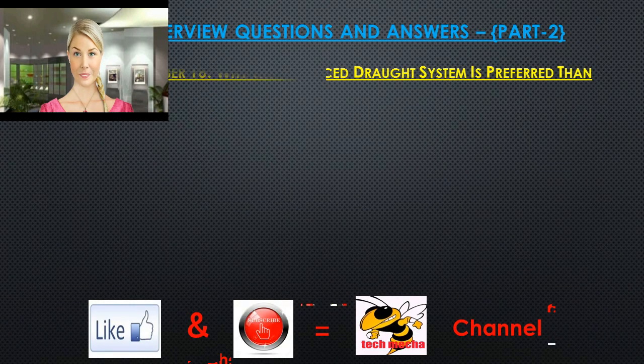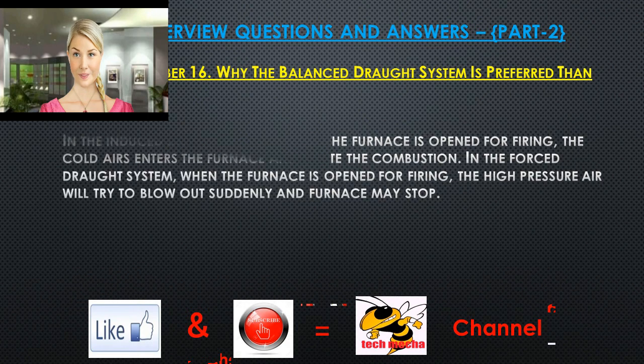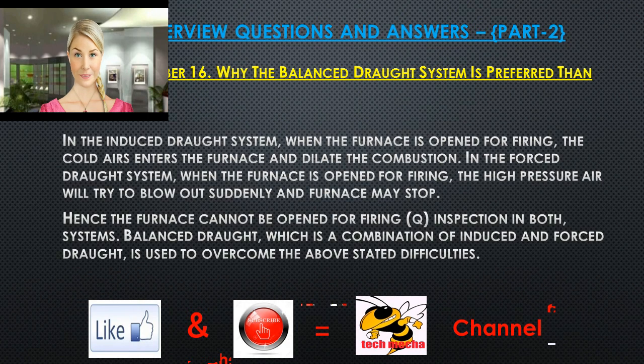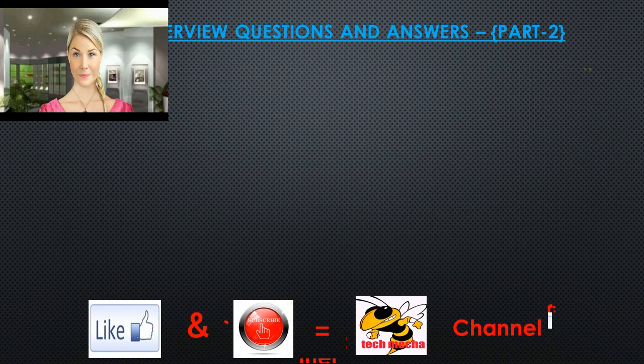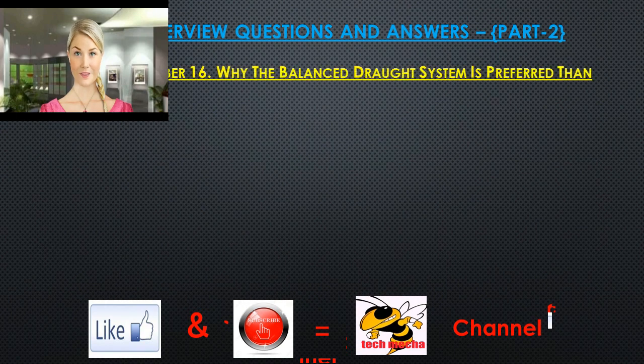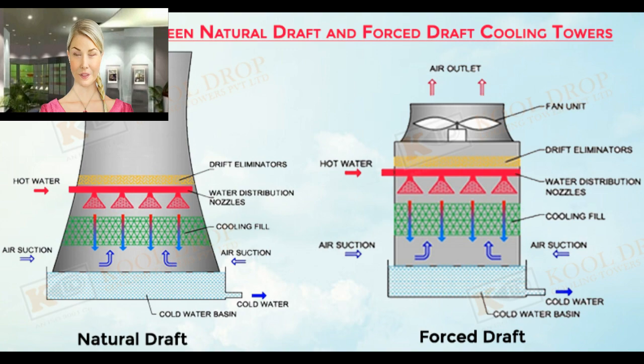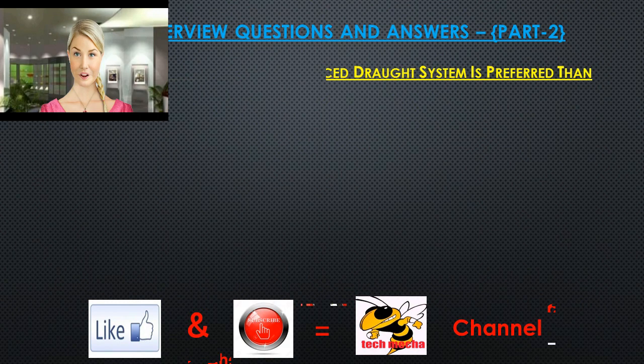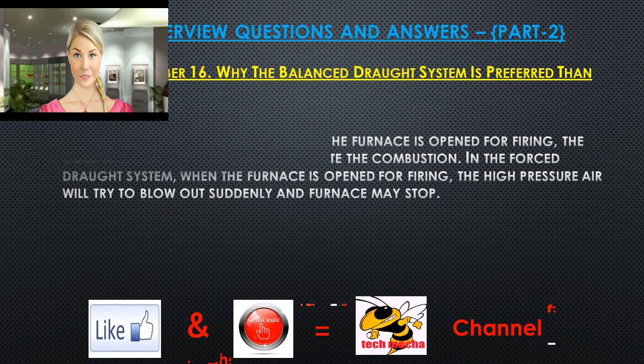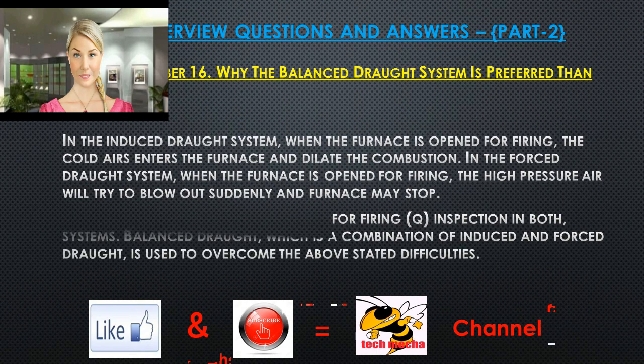Question 16: Why is the balanced draft system preferred over other systems? In the induced draft system, when the furnace is opened for firing or inspection, cold air enters and dilutes the combustion, which may stop the furnace. To overcome these difficulties in both systems, balanced draft — which is a combination of induced and forced draft — is used.